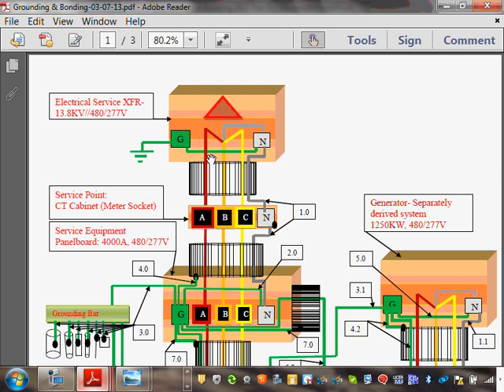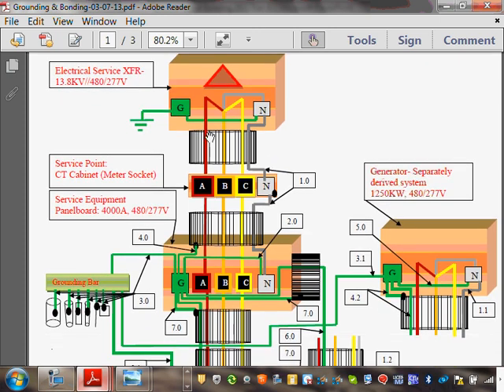Okay, so this transformer happened to be primary 13,800 volt. Don't let this scare you. That's utility owned and operated in this side. On this side, the secondary side of your transformer, 480/277, that's my transformer. Now, the utility will operate and ground the transformer when you have a grounded system. So you come down, then you bring a conduit from the transformer into the meter socket.